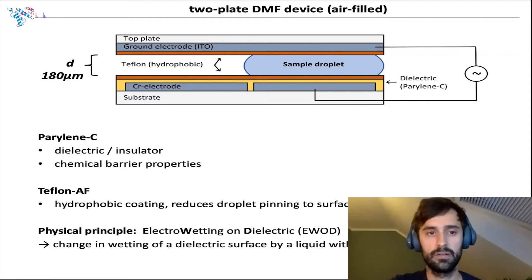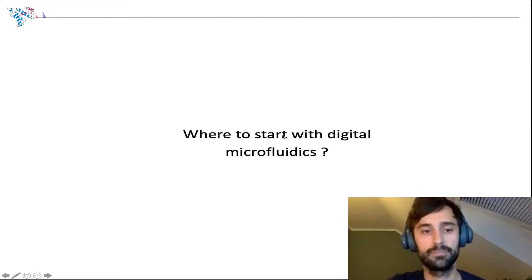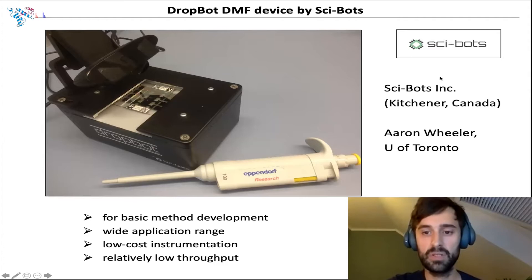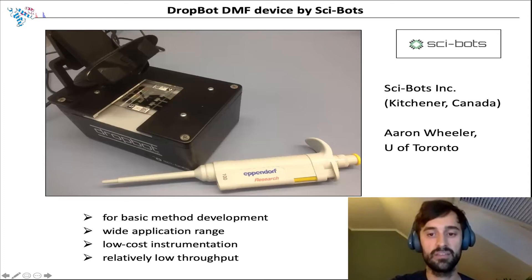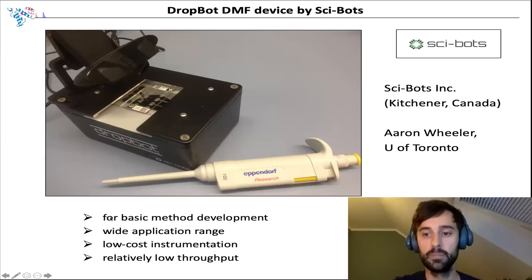Where to start if you want to do digital microfluidics? We found a small box called DropBot from a startup company, Sci-Bots, which is kind of a spin-off of Aaron Wheeler's research group at the University of Toronto. Aaron Wheeler is one of the pioneers of today's DMF. This device has quite a small footprint, is cheap, and contains all the electronics you need. I would consider it a tool for really simple, basic method development, with a very wide range of applications, though the throughput is not so high.